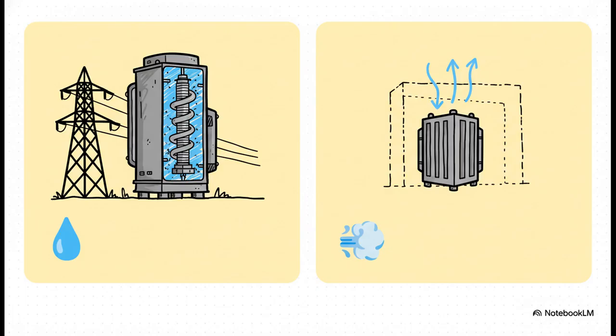First, you've got your oil-immersed reactors. They look a lot like giant transformers, and they're used for the really high-voltage stuff. Then you've got dry-type reactors. These are cooled by air, and you'll find them in places where a big tank of oil would be a fire risk, like inside a city substation.